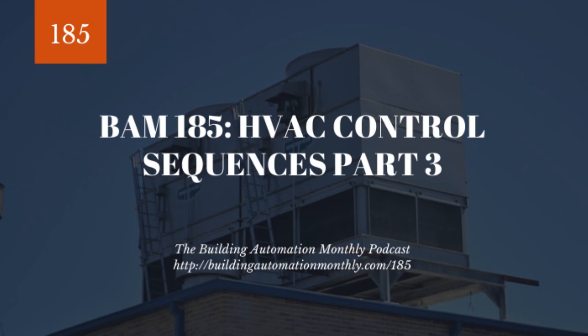I really recommend if you're programming any HVAC system that you have some form of maintenance mode where basically you disable alarms. That way folks can work on the system and not be triggering the slew alarms and causing all sorts of issues. Okay, so we've got that. We've got our three occupancy modes, right? And within our occupancy mode of occupied, we have heating, cooling, and ventilation. Let's take a look at these.